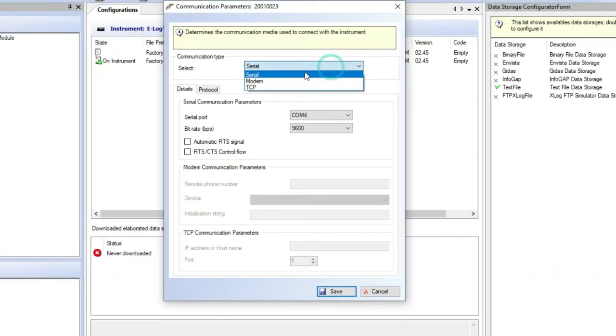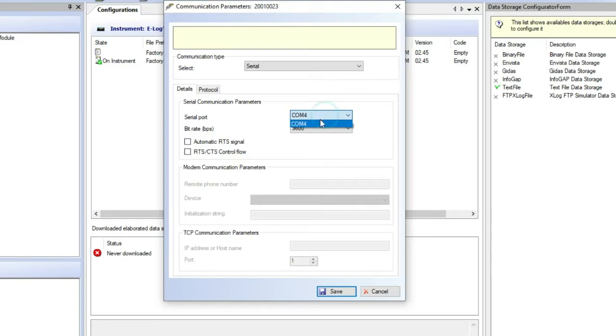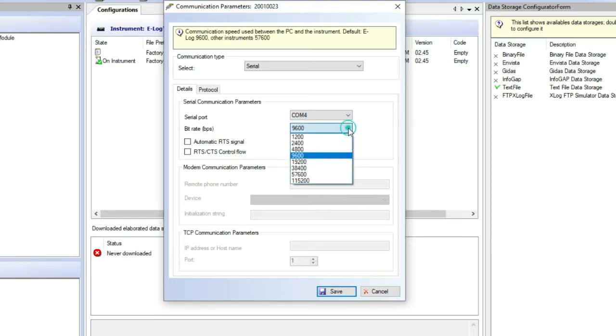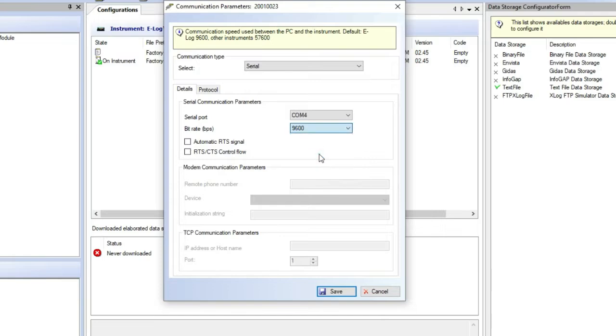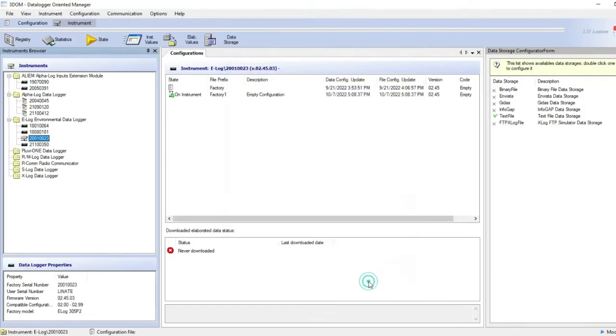Right-click and select communication parameters. Communication type must be serial. Serial port is PC port number assigned to the USB adapter. Bit rate, 9600 bit. Save it.